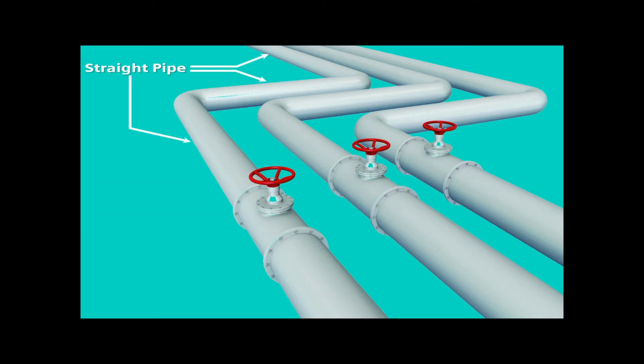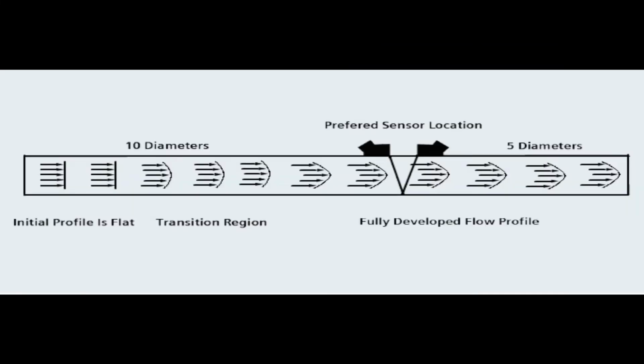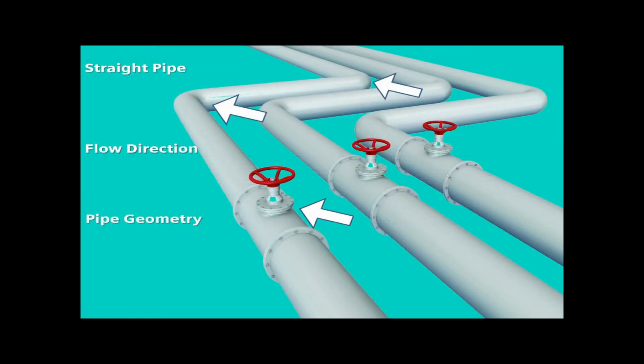Straight length of pipe is always the first consideration, as sufficient straight pipe upstream of the flow meter will ensure a symmetrical or fully developed flow profile, providing the best measurement conditions. The flow direction must also be considered for placement of the sensors relative to the straight pipe section, to provide as much upstream straight pipe as possible. But how much straight pipe is sufficient? Well, you may have heard the old industry standard of 10 diameters upstream and 5 downstream, but is that really sufficient? That brings us to piping geometry.